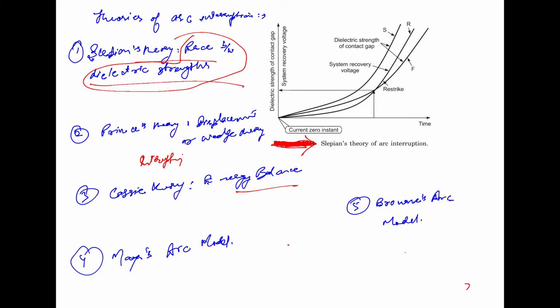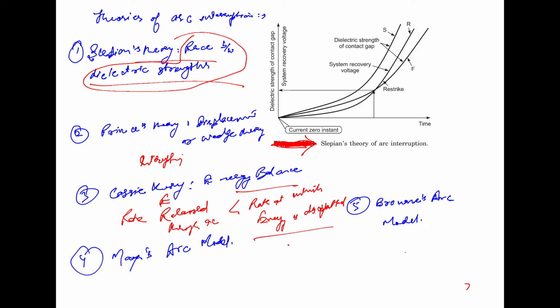According to this theory, if the rate at which the energy is released through the arc is less than the rate at which the energy is dissipated by the arc interruption arrangement, then the interruption succeeds under this condition.